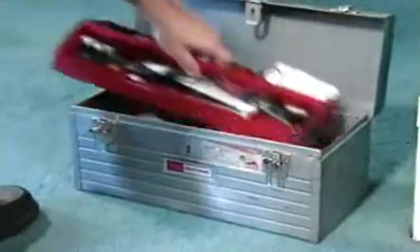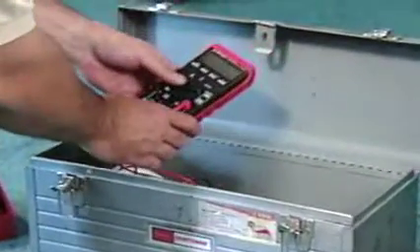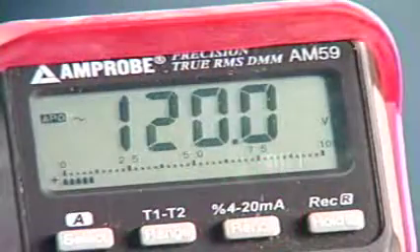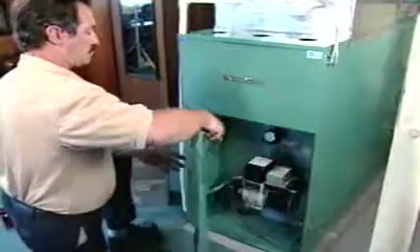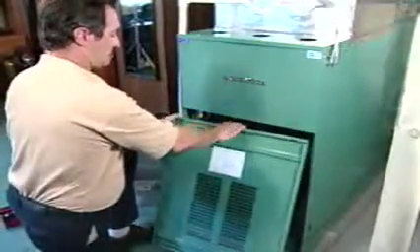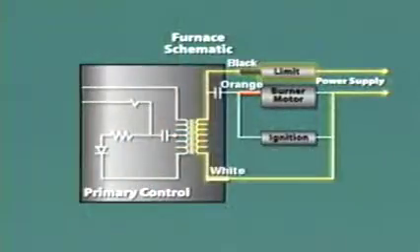The unit should be operating. First, check to see if it's getting power. Since the furnace receives voltage through the service switch, start there. Turn the service switch off and remove the cover. Start by placing the meter leads across the line side disconnect terminals. The reading of 120 volts is good, so replace the disconnect cover.